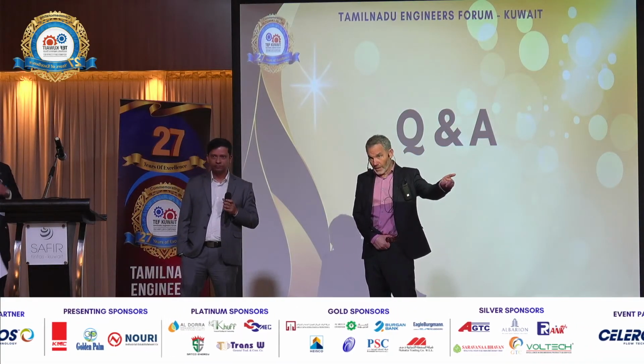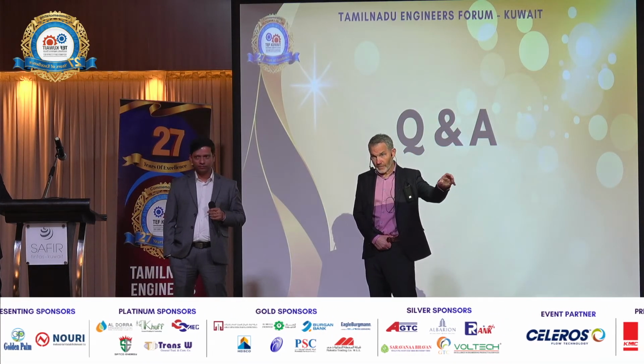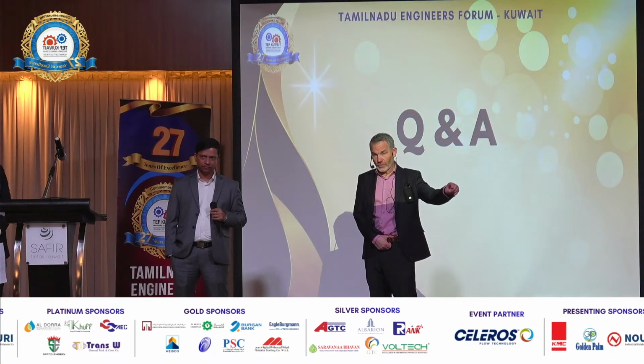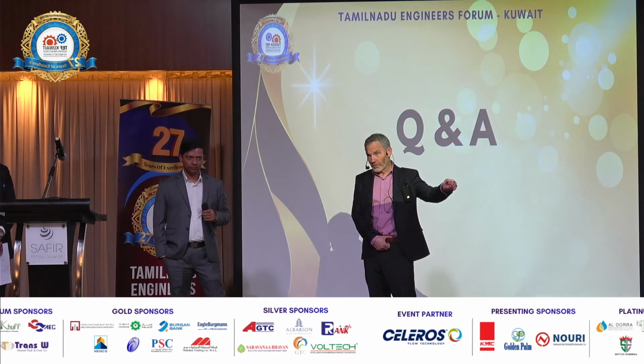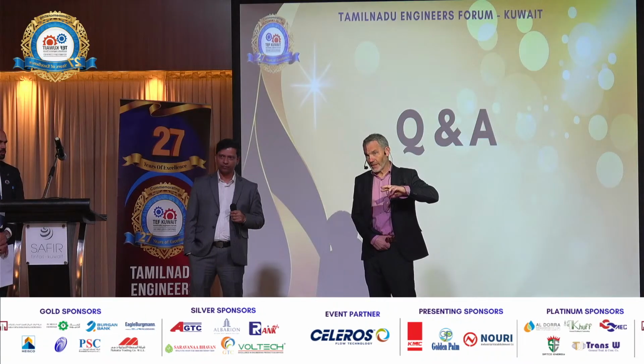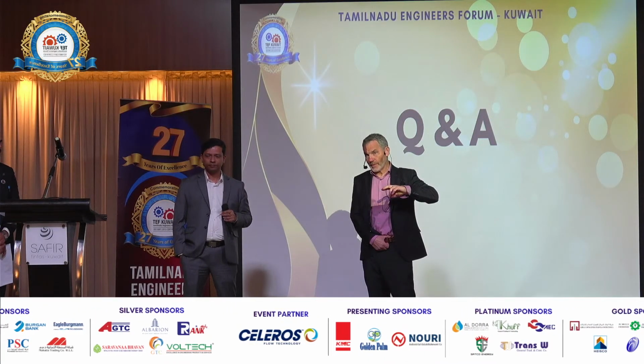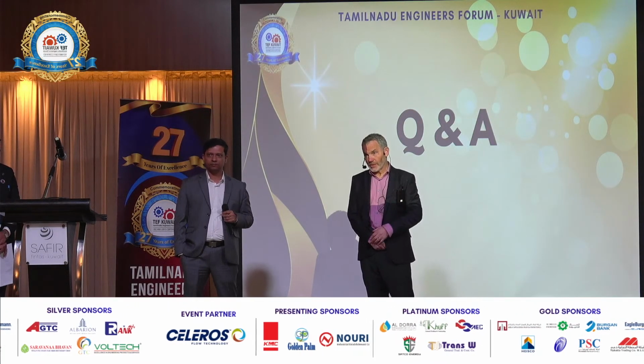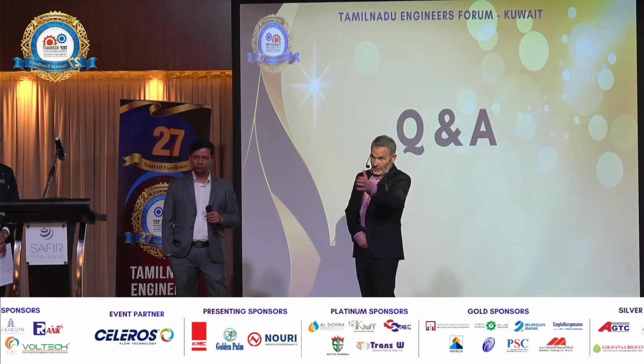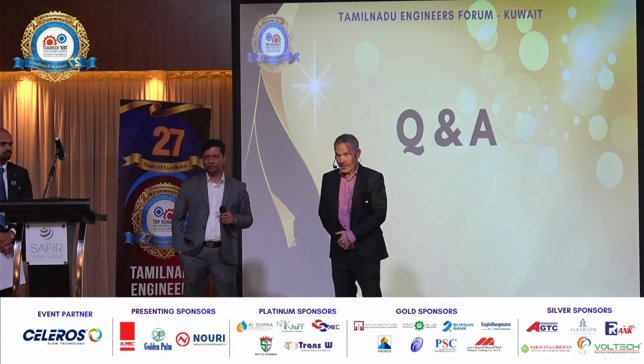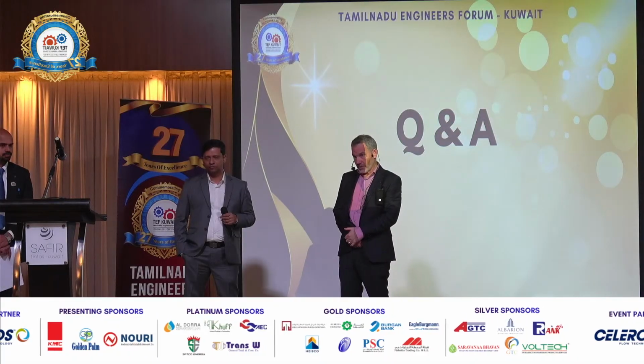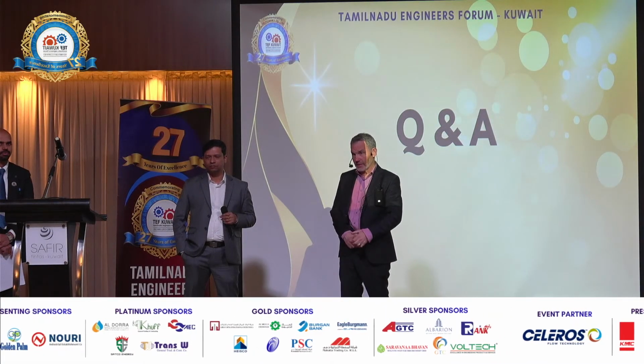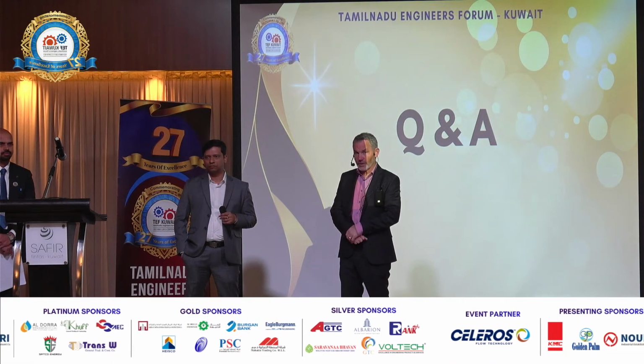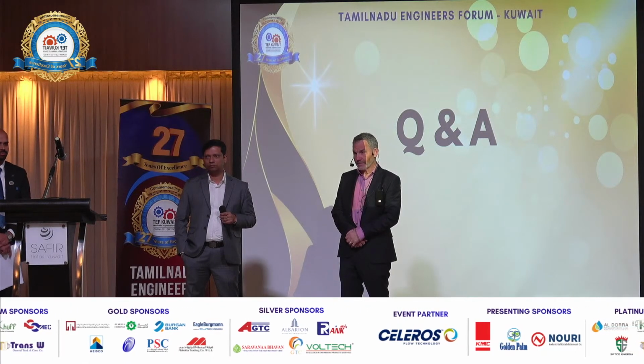And the case study that was up, that was a 50% reduction in flow. That was the one Scott worked on for the North Sea just last year. Yeah, that was a Sulzer pump, so that was a big change in the hydraulics. That's us bringing the best efficiency point down to 40-50% flow. So it's definitely possible, and we've done it quite a lot.